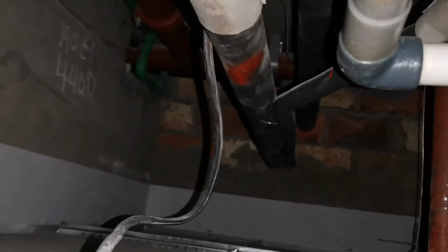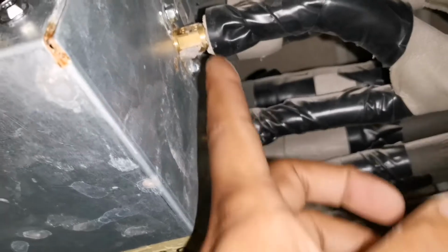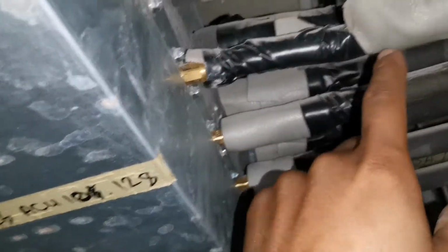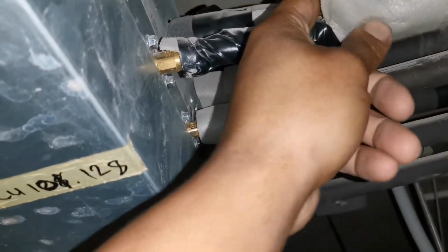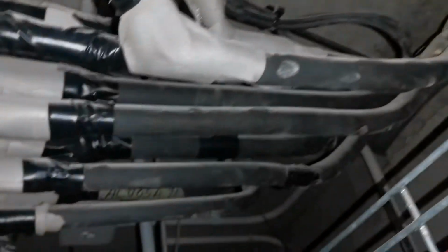Yeah, so your main lines come in over there. And inside this box you've got a cooling and heating solenoid for each port. So it'll be port A, B, C, D, E and F. Now this is a dual port, so there's a Y joint here joining to one. That's mainly because the capacity for each of these might not be sufficient for the indoor unit that this piping goes to. So therefore these are combined to make up for that capacity.